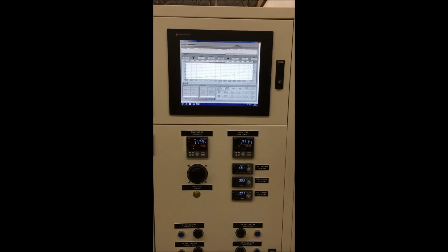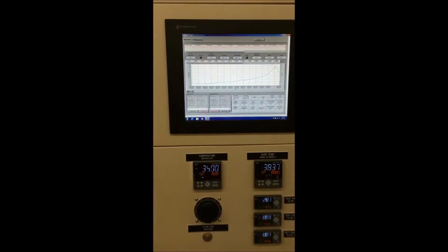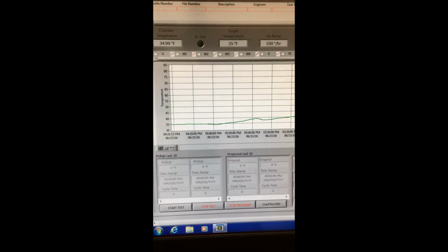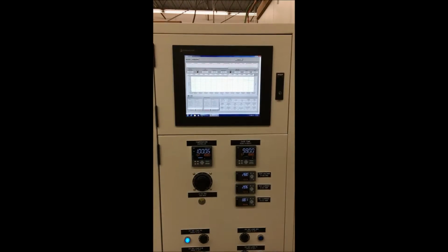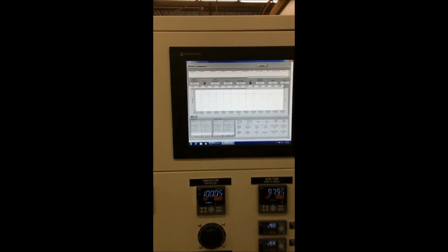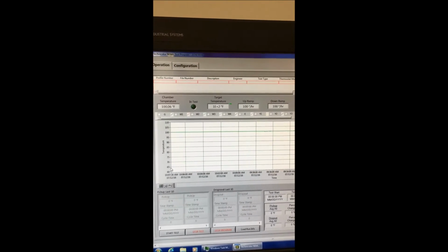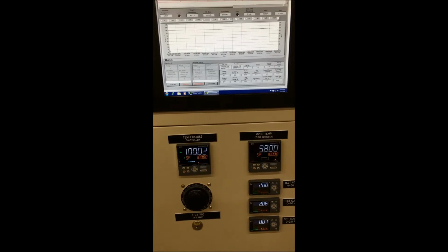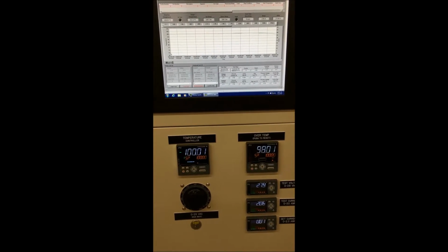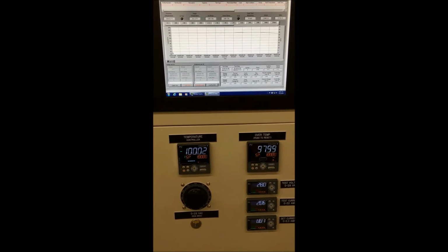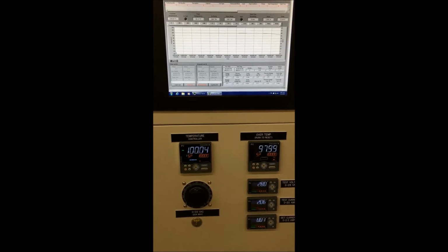Here's the chamber running at 35 degrees. As you can see, a very flat line. And here's the chamber running at 100 degrees Fahrenheit. Also, very stable, flat line. Notice there's a slight discrepancy between the overtemp controller and the temperature controller. That's because they're in two different locations.